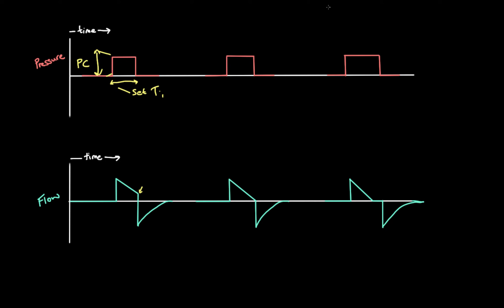In pressure control, we set a pressure and as a result we get a tidal volume. Tidal volume, VT, varies in pressure control. We talked about compliance — how stiff the lungs are. If they're very stiff, a given change in pressure results in a smaller volume. If the lungs are easy to open, the same pressure change results in a bigger volume. The parameters we set in pressure control — the pressure and the inspiratory time — are going to determine the tidal volume, and we need to be able to manipulate that.